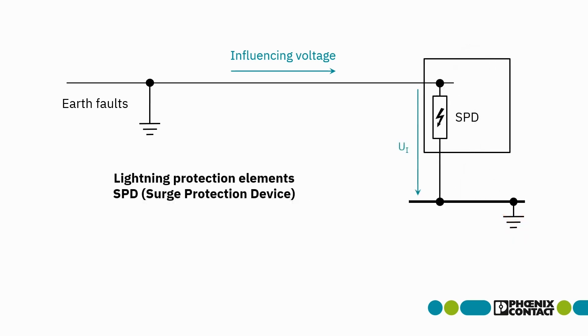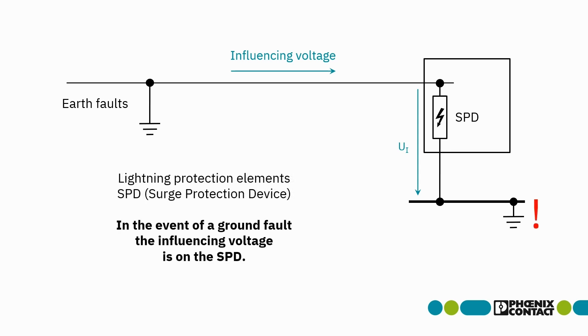Now we come to the effects on devices, for example lightning protection elements — in other words, SPD surge protection devices. SPDs must be earthed in order to function properly. This means that the influencing voltage is applied to the SPD in the event of an earth fault, and this must be taken into account when designing SPDs.